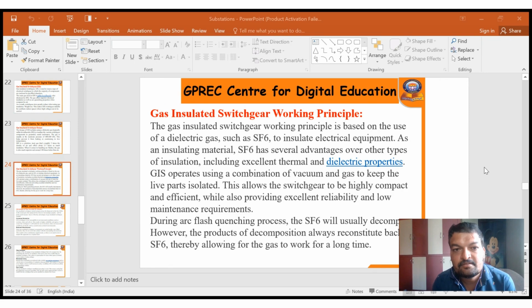GIS operates using a combination of vacuum and gas to keep the live parts isolated. Whenever any operation is going on, the main purpose of the gas is to combine with the vacuum so that it keeps the live parts isolated while also providing reliability and requiring low maintenance. Why? Because it has very high insulation. Because of this high insulation property, it requires less maintenance as compared to the air insulated substation.